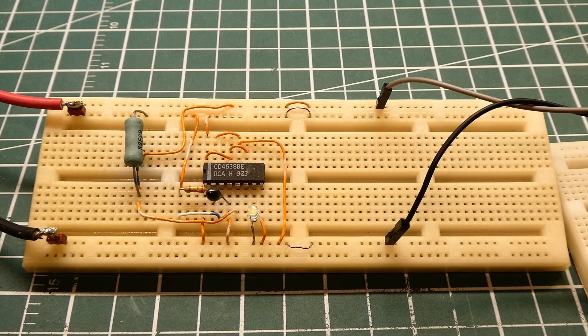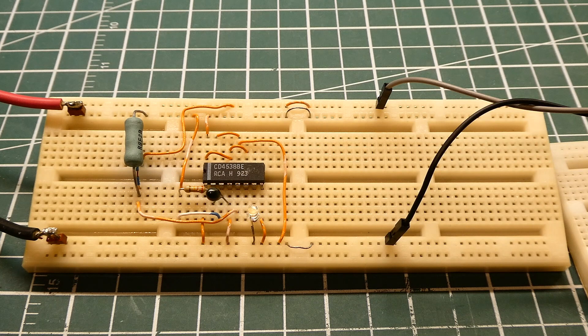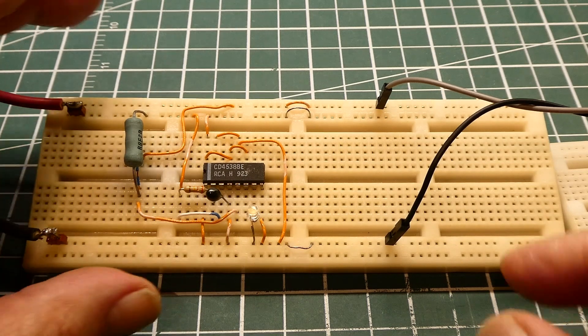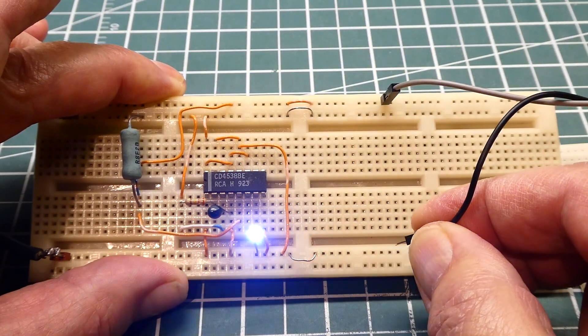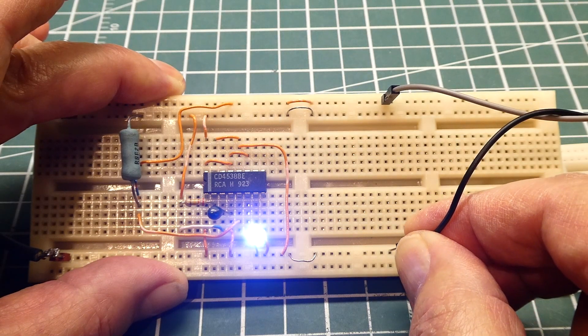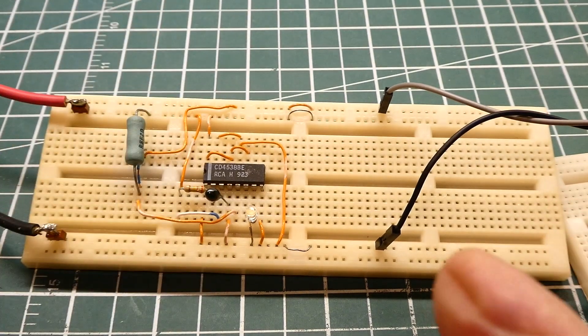Now the detecting circuit is fail-safe. If the twisted pair gets cut so it goes open or gets shorted, the alarm will go off telling us there's a problem we have to go out there and investigate. So if I pull off one of the wires indicating an open circuit, so say the wire gets cut, the alarm will go off. Tell us there's a problem. Now if I put it back it clears.